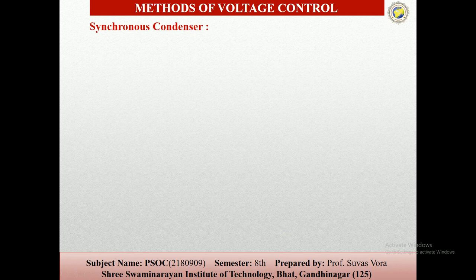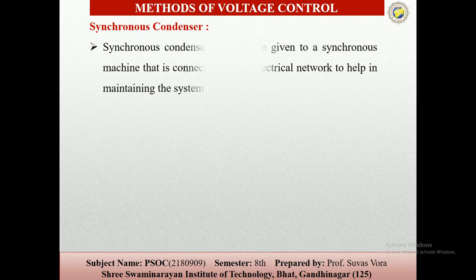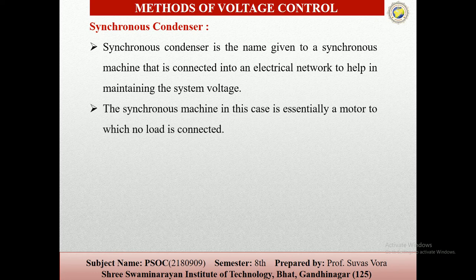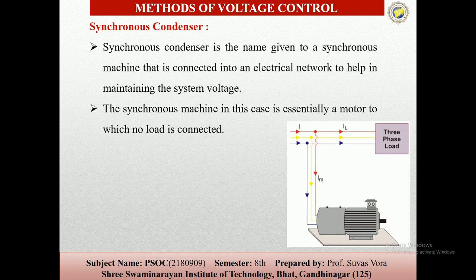Now we can study the synchronous condenser. A synchronous condenser is nothing but a synchronous motor used as a synchronous condenser, and this synchronous motor provides leading kVA to the transmission lines, which is a source of lagging kVA. The name synchronous condenser is given to a synchronous machine connected into the electrical network to help maintain the system voltage, and the synchronous machine in this case is essentially a motor to which no load is connected. So here you can see the synchronous condenser system.